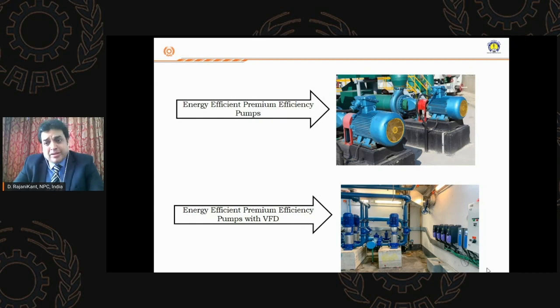I personally feel, out of my experience, that these are not taken care of properly. Once it is designed and erected in the plant, nobody bothers until it goes for a breakdown. The capacity of the pump is one major issue: the design should match the actual requirement, or else the oversized capacity of the pump will lead to damper operation, which is an inefficient way of operating your system. So it increases your power consumption. If your pump is oversized and you are an SME, you cannot replace the pump. In such a case, you can go for a VFD if there are variations in the loading of your plant.